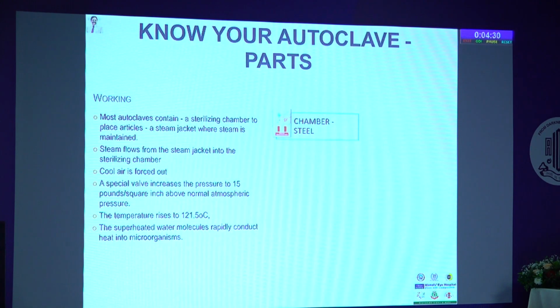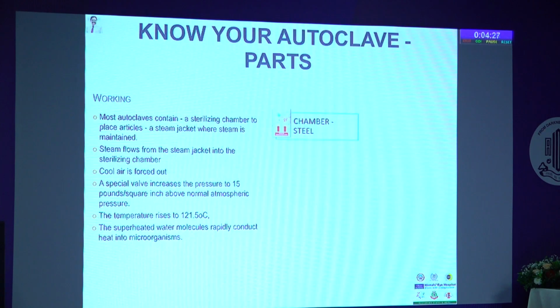So before deciding to buy or looking into an autoclave, you have to know the parts of the autoclave. Since the principle is the same, the chamber is very, very important. Most of us buy steel chambered autoclaves. This has to be medical grade so that it doesn't rust. And you have to have a secure lock. Most of the accidents happen because the locking mechanism fails.